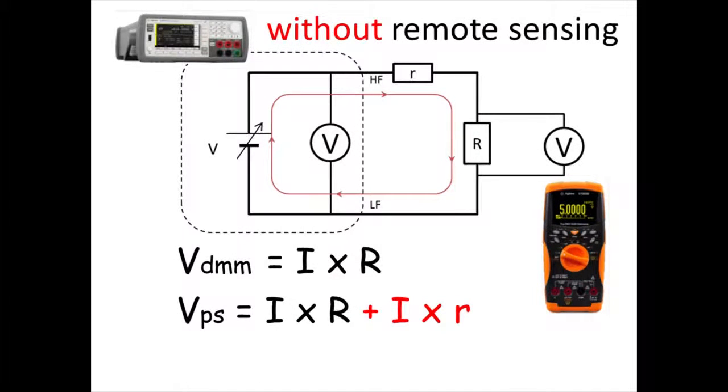In case you don't use remote sensing, the monitoring voltage of the power supply contains the applied voltage of the lead resistance. Therefore, the power supply cannot know the actual voltage applied to the DUT.